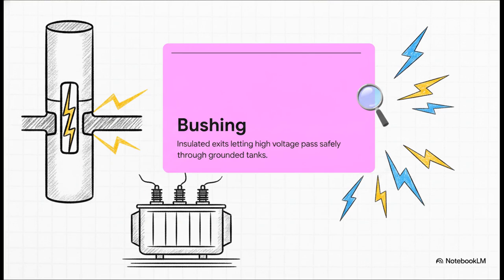By definition, bushings are insulated exits. They're engineered to let a high-voltage electrical lead pass safely right through the grounded steel wall of the transformer tank. And you really have to remember, that tank is grounded steel. If the energized lead gets too close, the electricity will arc directly to the tank. So the bigger the voltage you're dealing with, well, the longer and fatter the bushing has to be to give you enough insulation distance. Because if a bushing fails, you've got a direct catastrophic fault to the tank wall, and your transformer is instantly taken offline.